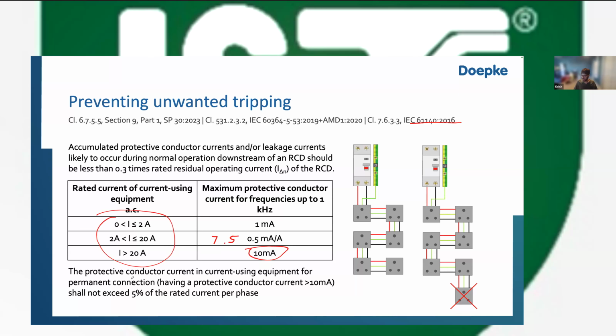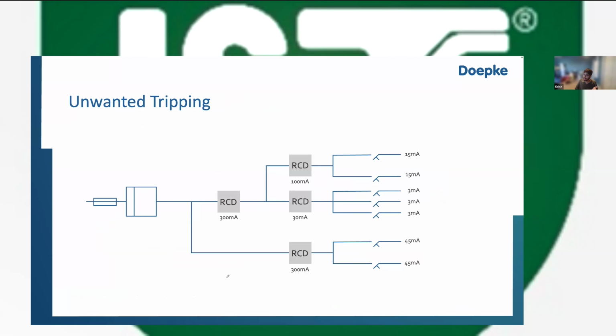But the important thing for you is that for equipment for permanent connection, which is what an elevator is, having a protective conductor current greater than 10 milliampere, you're allowed to have it not exceeding 5% of the rated current. So for example, if your elevator is using 50 amperes, 50 amperes times 0.05, which is 5%, technically you are allowed even 2.5 amperes of leakage current for a 50 ampere device. And it can get tricky. Obviously, in practice, this is quite rare, but I've seen 300 milliampere, 500 milliampere on a certain elevator, especially those with regenerative drives. How do you prevent unwanted tripping?